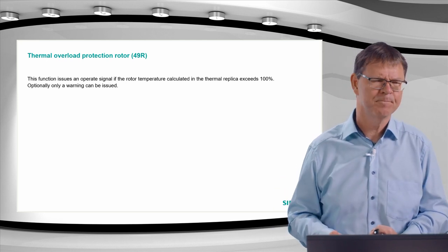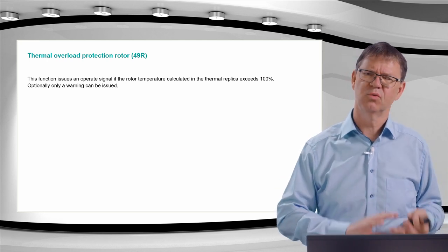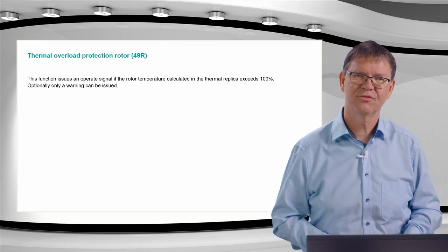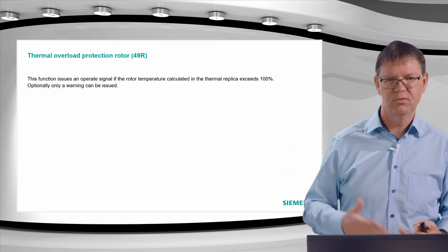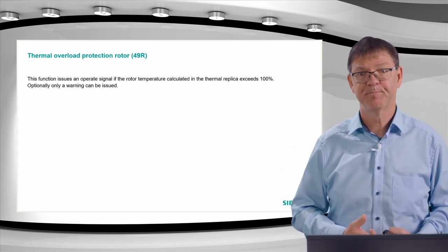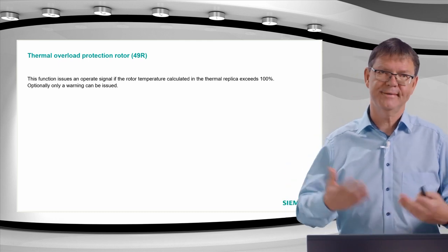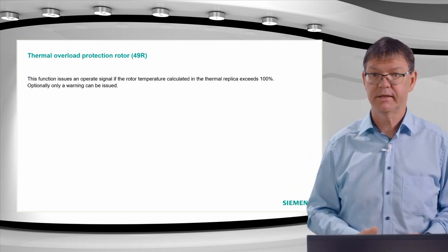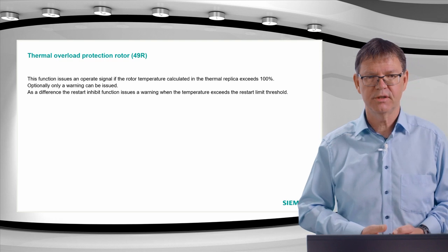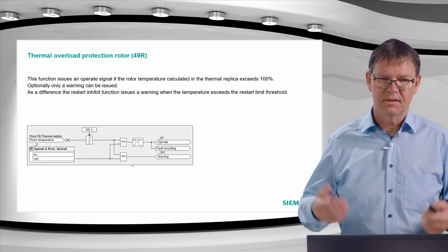On the other hand, if your process maybe is more important than a couple of percent of the rotor temperature, then you would maybe trip with this function at the end of a restart, and this would be maybe not desired. So it depends on the application here. Yeah, it's a very simple thing.